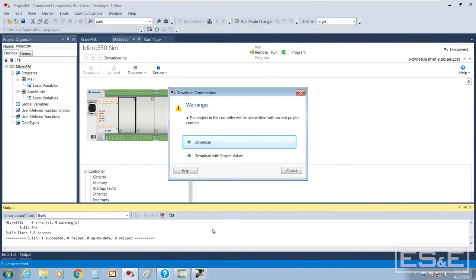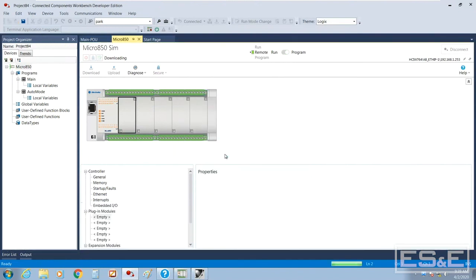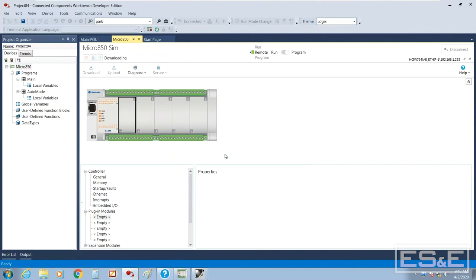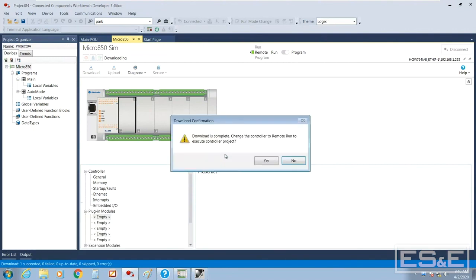If you want to download your project values, what you've already set up in your projects to the controller, then you can hit download project values and that's what we're going to do. We don't really have any values in the program but that's kind of a cool feature. There's the data preservation tool in 5000 that allows you to do that, but that's a completely external utility, so it's just kind of built into CCW. A really cool feature if you need to maintain the data inside your controller.